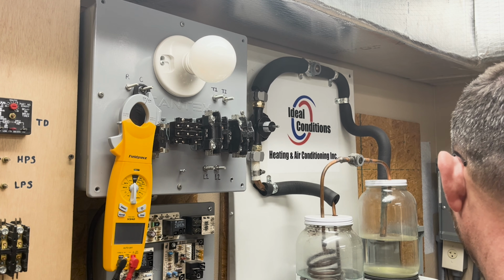I'll just take this green wire off too, just to clean it up a little bit. So you can see once I push the contactor in, we have a full 240 volts, right? Because we're only breaking on this one side. I want to demonstrate that there's power here, power here, power here, check that out.